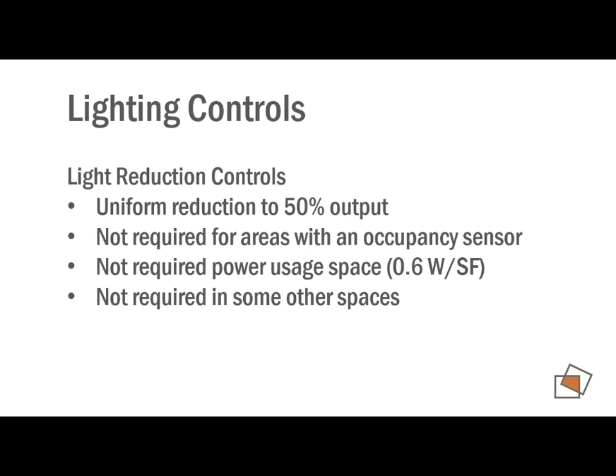The first thing the code tells you is in certain scenarios you have to be able to reduce the lighting level, and it has to be able to be reduced in a uniform way to a 50% output. So it could be just dimming all the fixtures, which is probably the method that we're going to use with the advent of LEDs and pretty cheap dimmable controls. But you could also switch alternating fixtures. If you had a big area, that would be acceptable too. And then there's some exceptions for it.